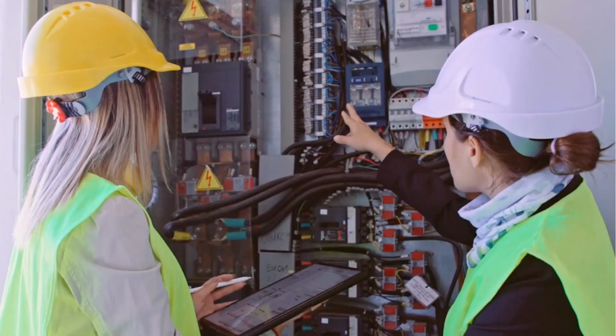Static completion processes will have gaps, with incomplete installations, missing equipment, missing instruments, missing documentation, and subsystems that do not align with the project startup sequences. This creates many snags that delay commissioning activities and impact your ability to meet the project in-service date.